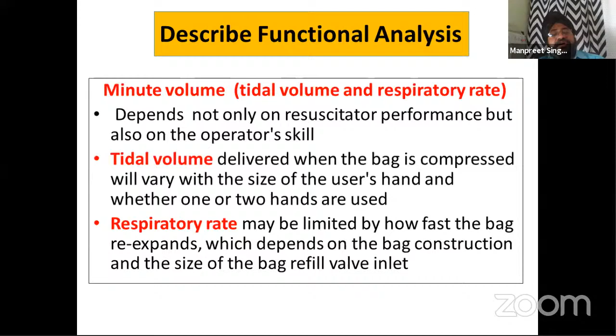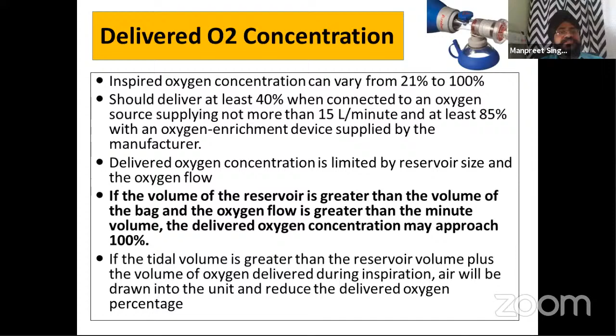The important thing is that the inspired oxygen concentration can vary from 21% to 100%, and it should deliver at least 40% when connected to an oxygen source supplying not more than 15 liters per minute. This is to be noted: if the volume of the reservoir is greater than the volume of the bag, and the oxygen flow is greater than the minute volume, the delivered oxygen concentration may reach approximately 100%. So you can give 100% oxygen also by changing the configuration of the Ambu bag.